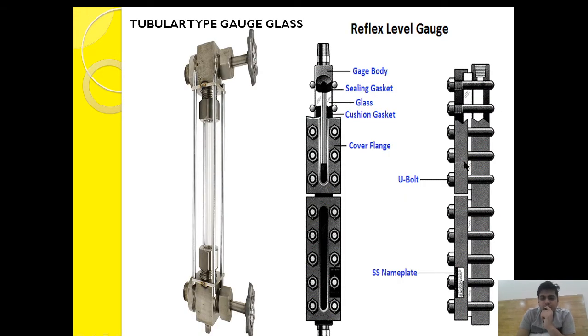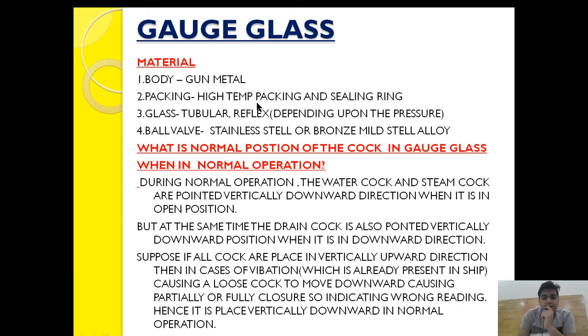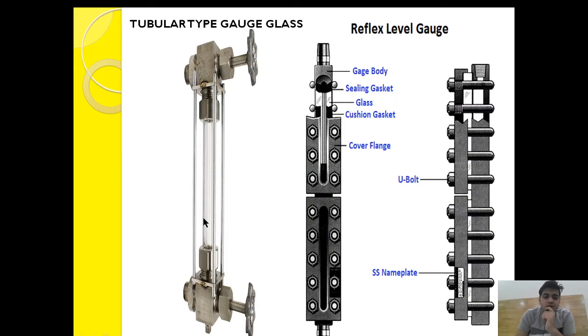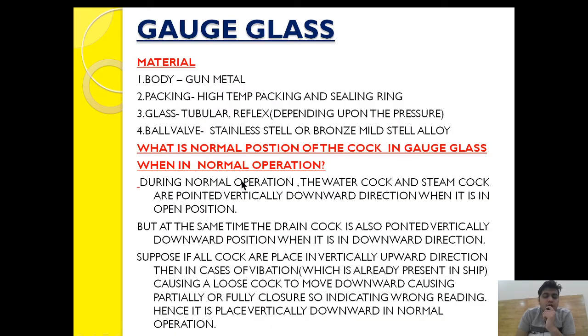The body of the gauge glass is mainly made up of gun metal. High temperature packing and sealing are used to ensure good sealing. The glass type depends on the type of gauge glass and the pressure and temperature — tubular glass for low pressure boilers and reflex or plate type for high pressure boilers. In the reflex type, the water level is shown in black and the steam space in white, whereas in the tubular type, the water level is shown as crystal clear white.